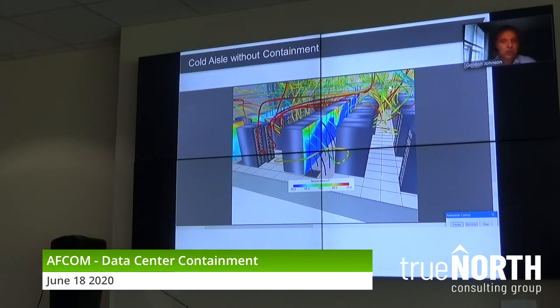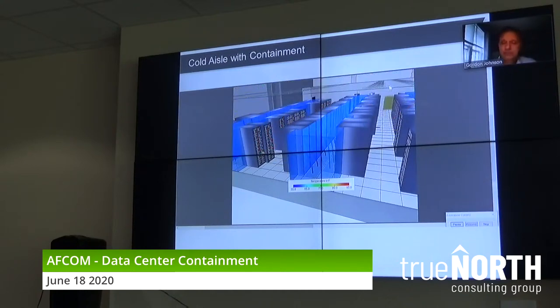And we look at this, we may say, how can I fix this problem? Well, you can't lower your temperatures anymore, and you can throw more air at it, but here's a real quick solution. Let's put cold aisle containment, exact same temperatures, data specs. Notice in the cold aisle, the cold air can't escape. It can't become bypassed air. It can't come up through the drop ceiling and return to the CRACs. It's got one place to go. It can only go to your server inlets.